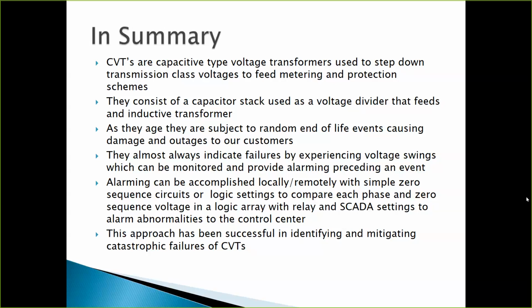And there's a side also asking the purpose of detecting failures in the CVTs. So the purpose is, if you saw that picture, the reason we want to detect a failure is we don't want to experience a catastrophic failure. What that does, it sends shrapnel, fire, it damages equipment, it causes an outage, it's hazardous to the employees, it operates your bulk electric system, it presents a whole other problem. So the purpose of detecting the failure in the CVT is to prevent that catastrophic failure. Another question?